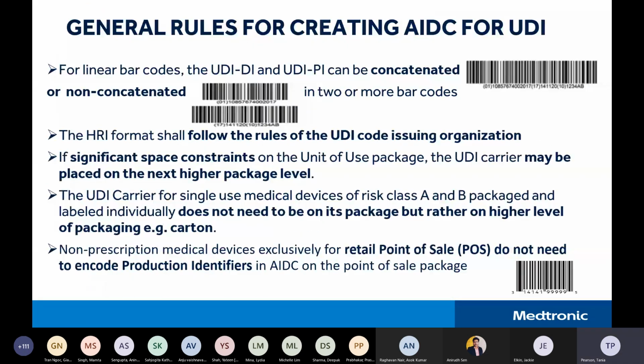So as far as the rules for creating the barcode, for linear, it can be concatenated, or you can break it down into two or more barcodes and have them stacked. But again, the human readable format should still follow the rules of the UDI code issuing organization. And if there are significant space constraints on the unit of use, the UDI carrier can be placed at the next higher packaging level, and we'll talk about that in a minute.